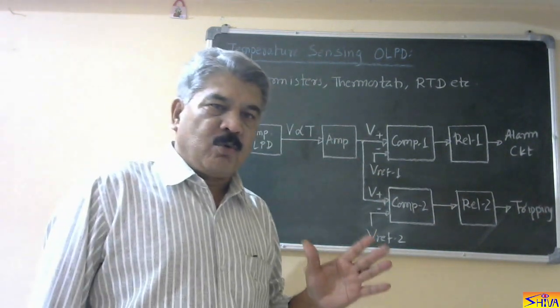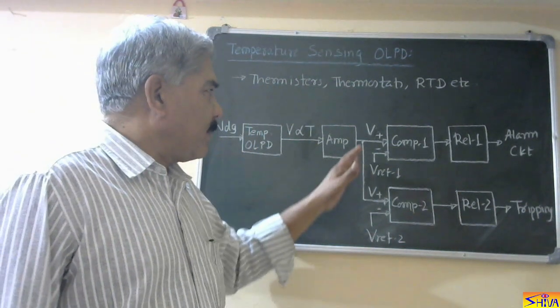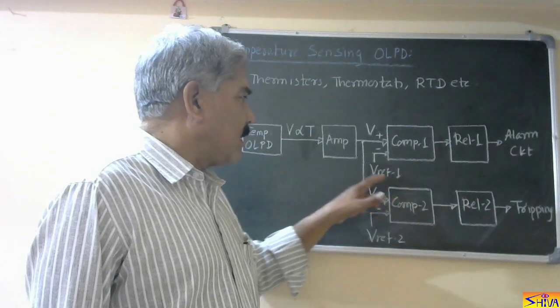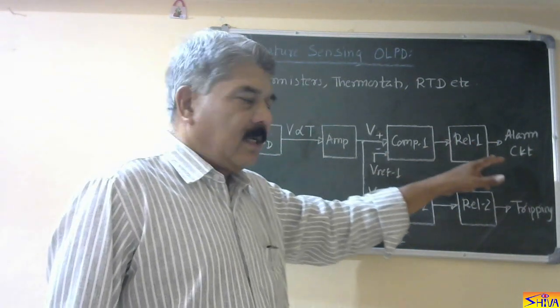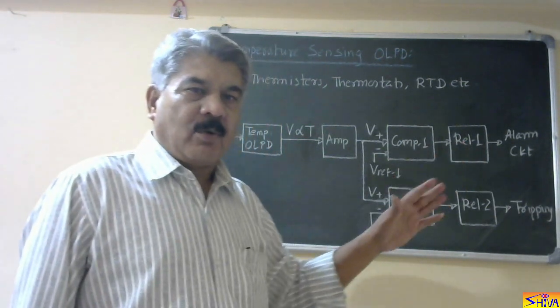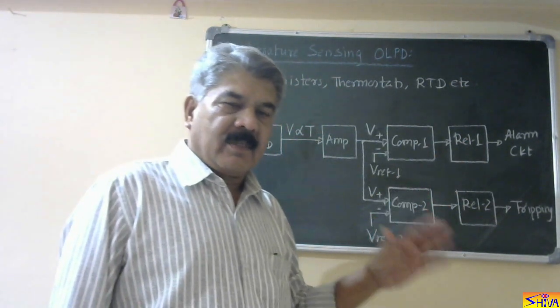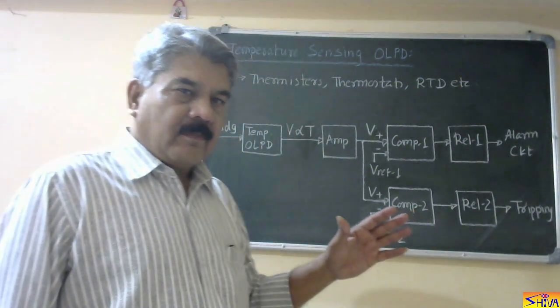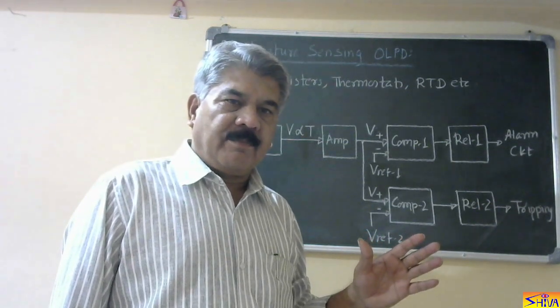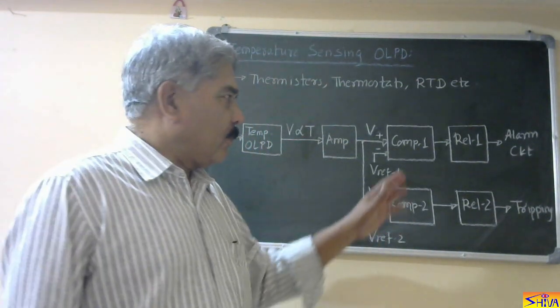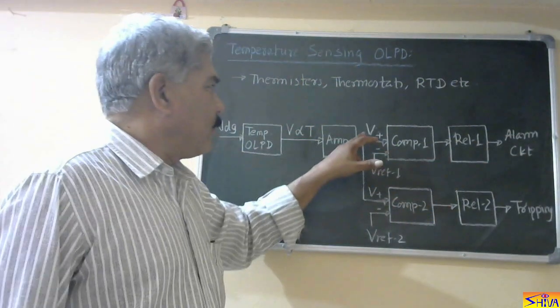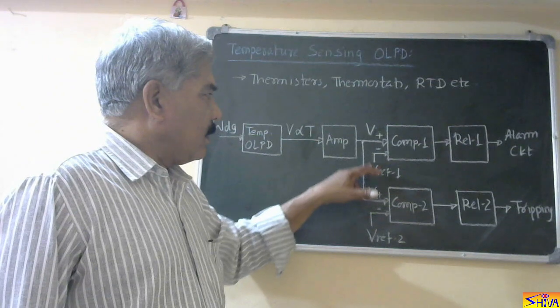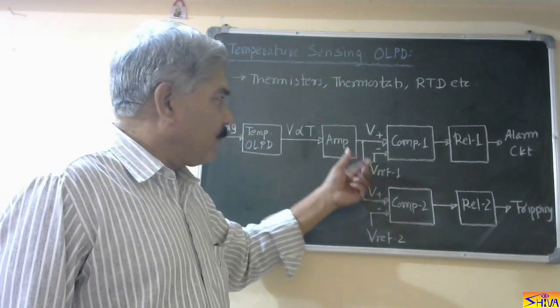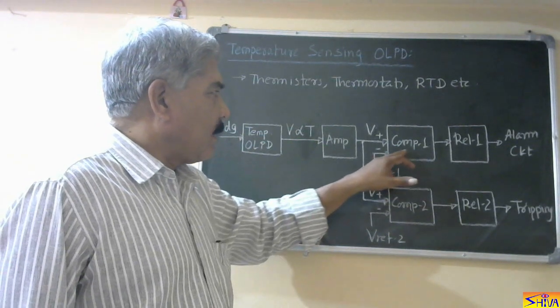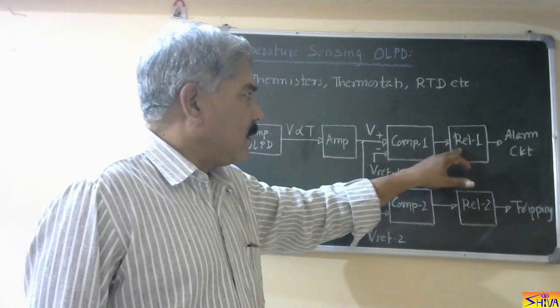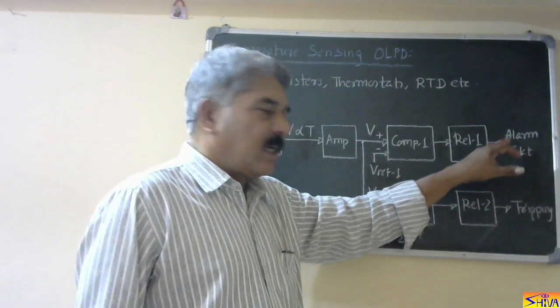Now there can be two systems. One, when temperature is increasing and crosses certain limit, at that time we need not trip the motor, because motor is connected to important system, important drive, important process. Therefore it is not advisable to trip the motor. So first is alarm circuit. So here we get the voltage. There is comparator. V reference 1 is proportional to some fixed voltage, and as soon as this voltage becomes higher than this, comparator 1 gives the higher output. This trips the relay, and this relay sounds the alarm in the control room.